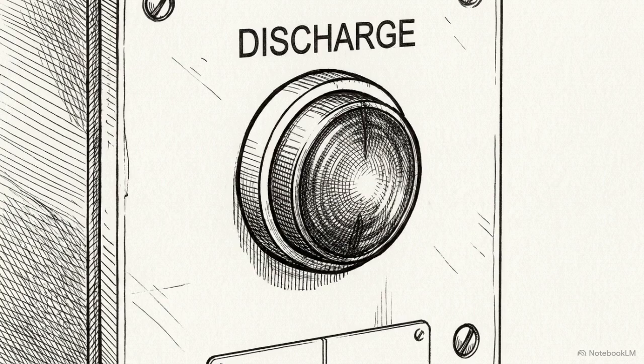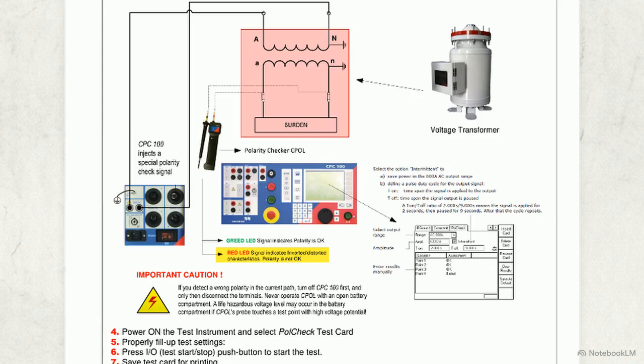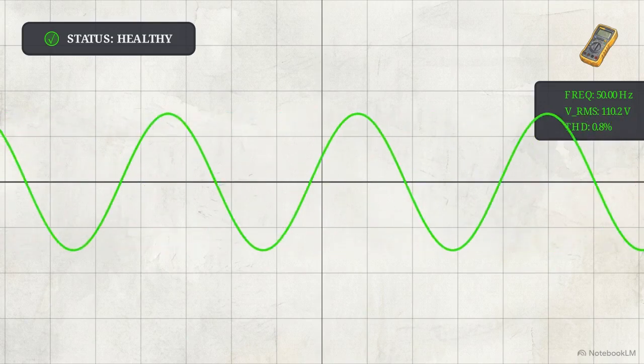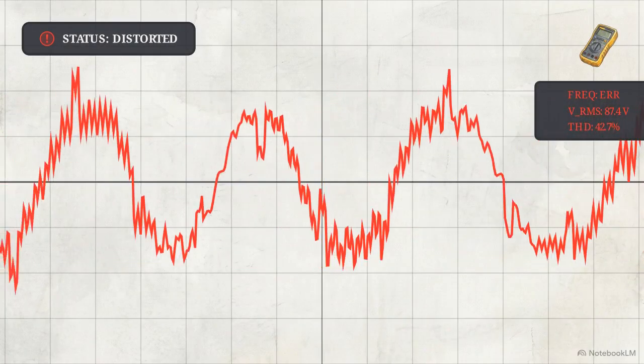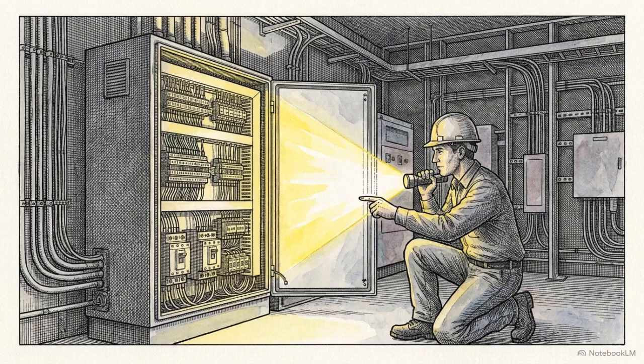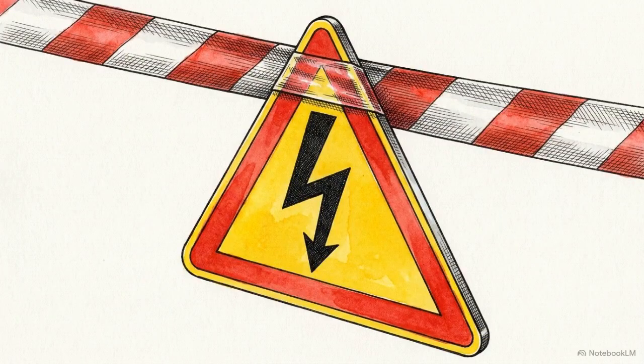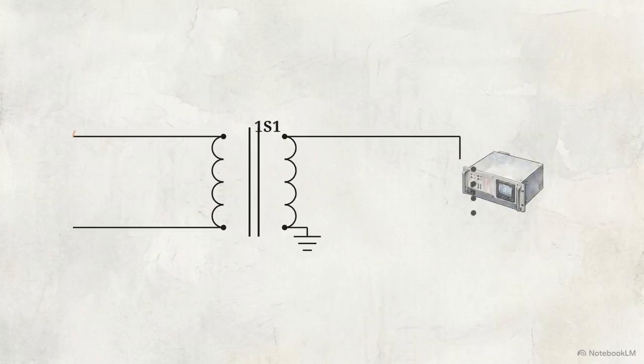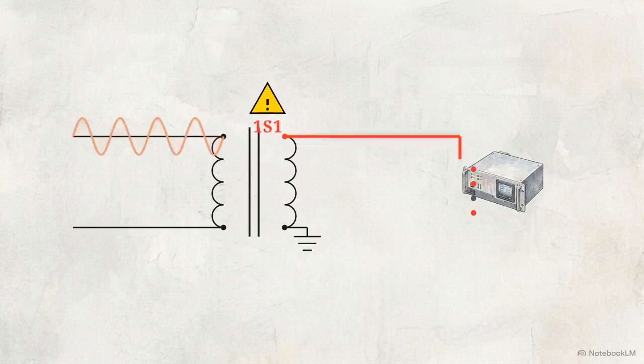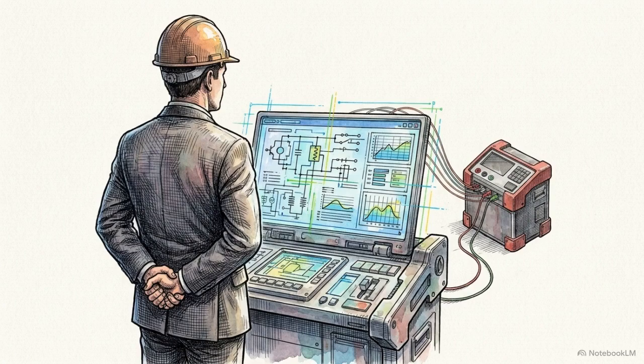Hazards also appear in signal diagnostics. When the polarity probe flashes a red LED, it doesn't strictly mean the wiring is reversed. It indicates a distorted characteristic in the signal wave. A distorted wave forces the engineer to halt the test sequence and hunt for unintended grounding points or parasitic capacitances hidden within the secondary circuit. High-voltage testing creates its own unique risks. During the withstand test, specific secondary terminals, like the 1S1 connection, can carry life-hazardous voltages if inadvertently left connected to downstream electronic relays. Modern test equipment dynamically manages lethal potential energy during the diagnostic process, requiring absolute operational discipline from the engineer.